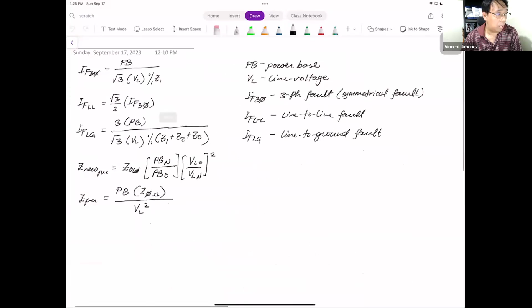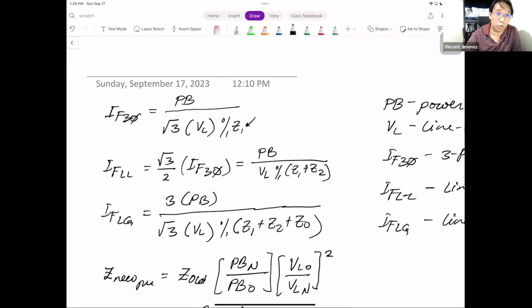If you want to use the formula, this is the general formula for line to line: power base, V line, per unit Z1, Z2. But since Z1 equals Z2, that's where the square root of 3 over 2 of your IF3 phase comes from. Because when you compare line to line with IF3 phase, the PB and VL cancel out, leaving 2Z1, so you're left with square root of 3 over 2. That's how IF line to line equals square root of 3 over 2 times IF3 phase is derived. I give that in detail in my lecture notes, in my course.